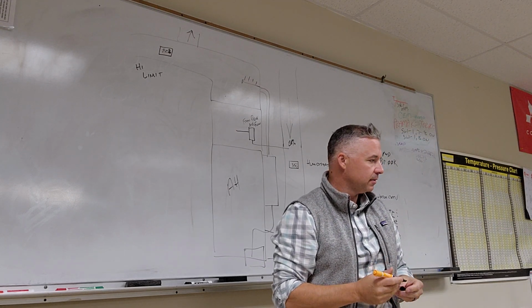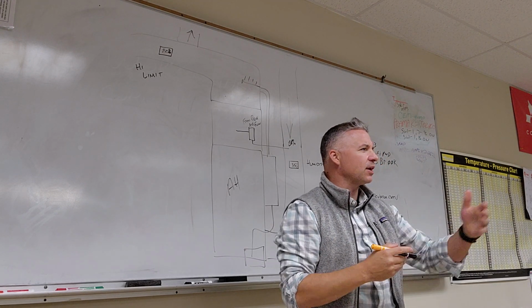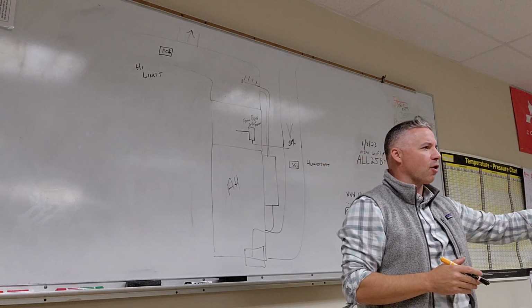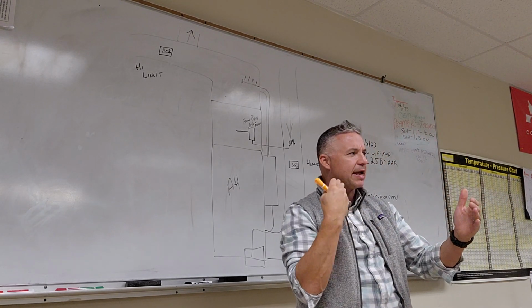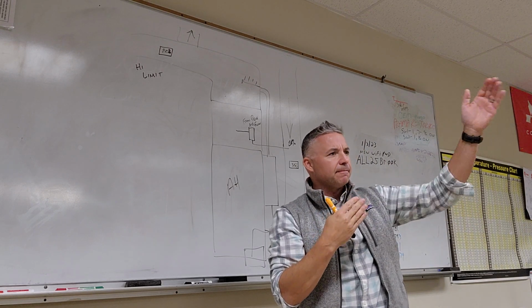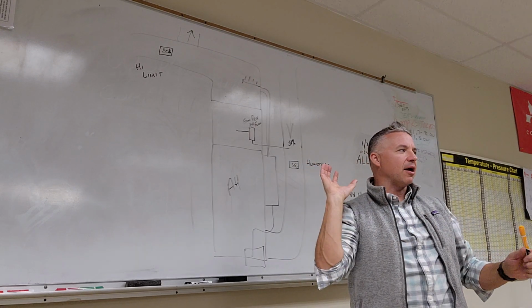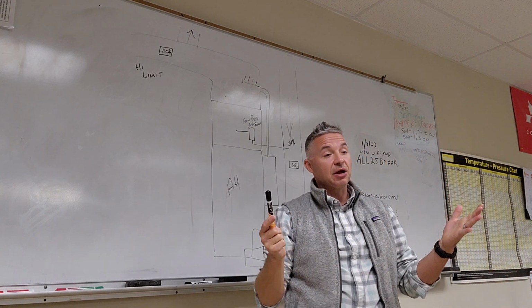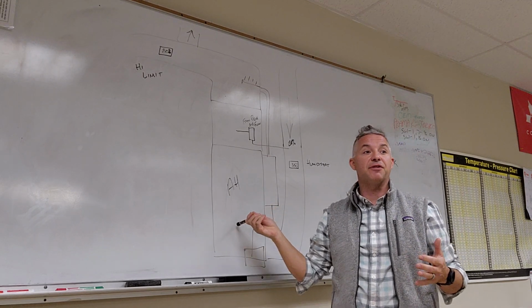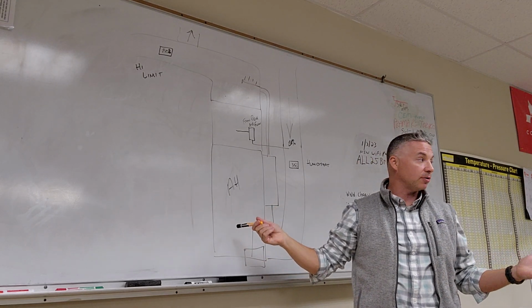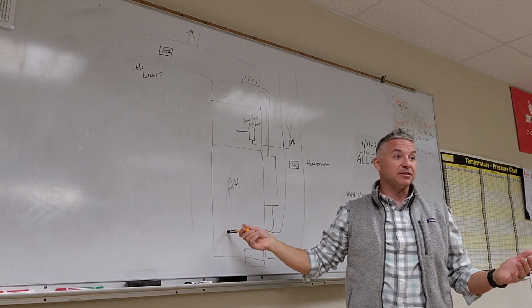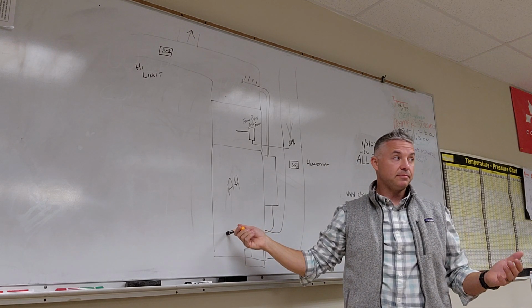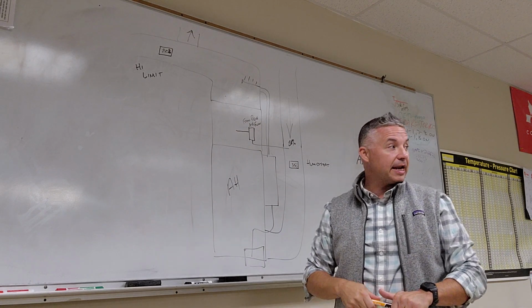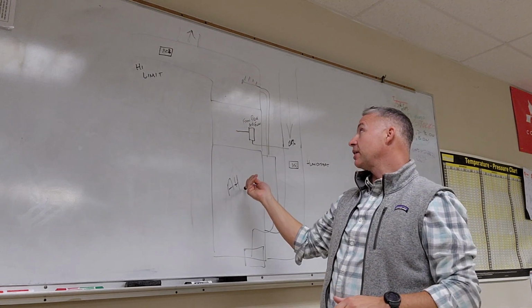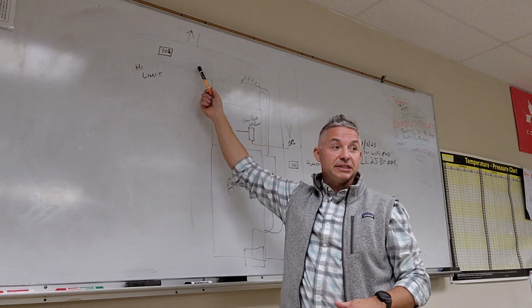Almost like a regulator or a metering device for our refrigerant, like something like that. It would create some back pressure, right? When that pops off, now you've just got all the steam pressure, tons of it blasting out in the ductwork. And in some cases, if you're running a very low fan speed, let's say the fan is on this air handler, just in the on mode, we're getting 50% fan speed if it's an ECM motor, right? We're not getting high CFM out of that. So at a very low fan speed with too much steam, you could also be saturating that ductwork.